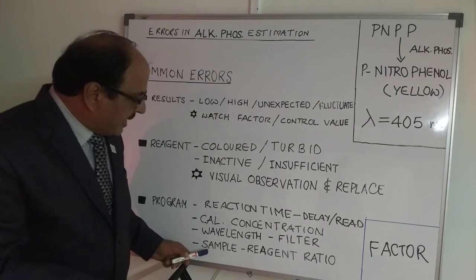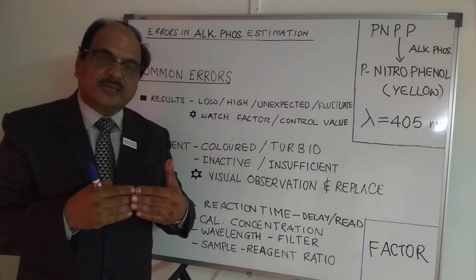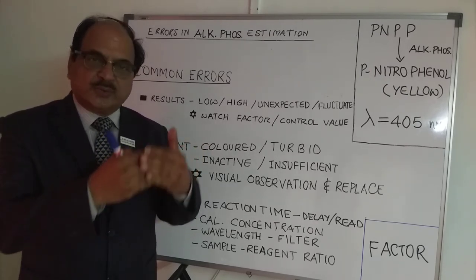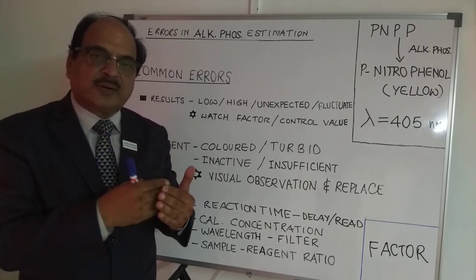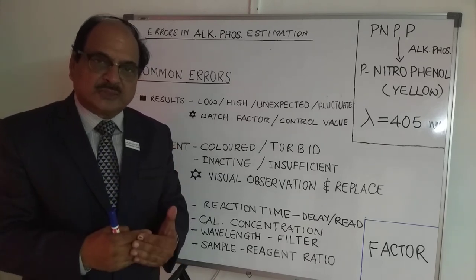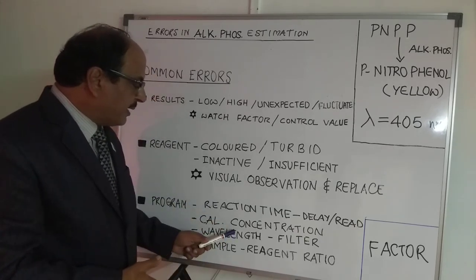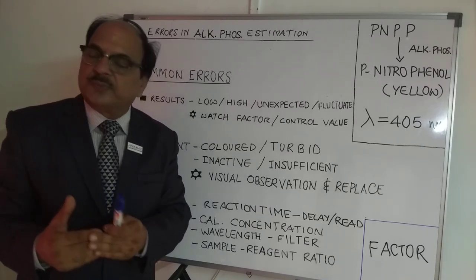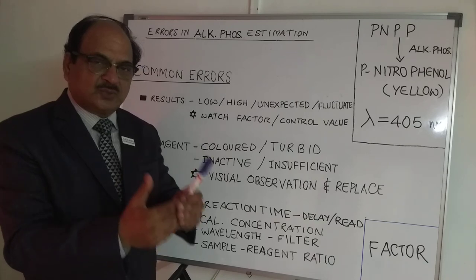Another important area is reagent-to-sample ratio. Alkaline phosphatase normally uses 1 ml of reagent with 20 microliters of sample volume. The maximum adjustment you can make is exactly half, maintaining the proportion — that is 500 microliters of reagent and 10 microliters of sample. If any ratio different from this is used, there is a possibility that calibration happened at one sample-to-reagent ratio while samples are run at a different ratio, which is bound to give you wrong results. Ensure that this ratio is followed.